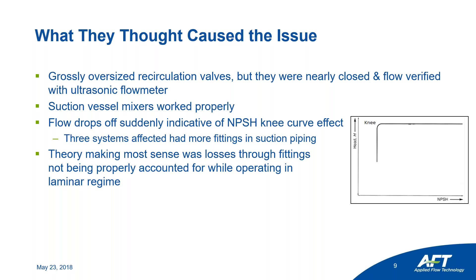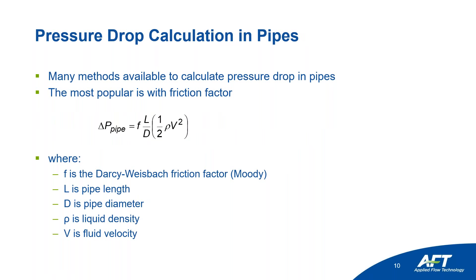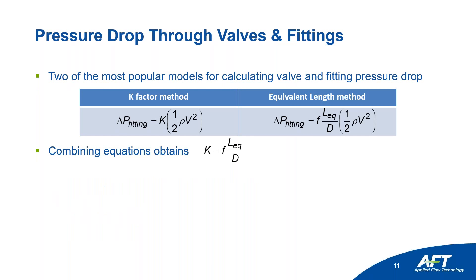So they decided to explore the loss calculations for fittings. For calculating pressure losses in pipes, the Darcy-Weisbach equation is one of the more popular methods. This calculation is the same regardless of whether it's laminar or turbulent flow — the friction factor differs for each regime, and Darcy-Weisbach accounts for both. For pressure drops through valves and fittings, there are two widely used methods: K-factors and equivalent lengths.